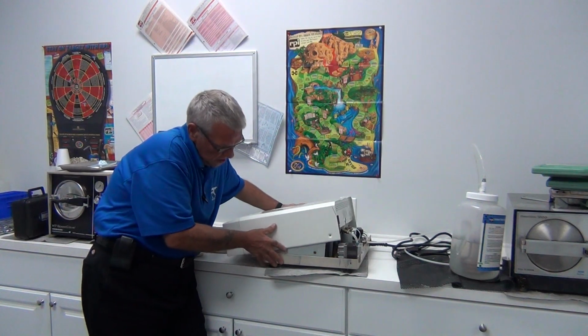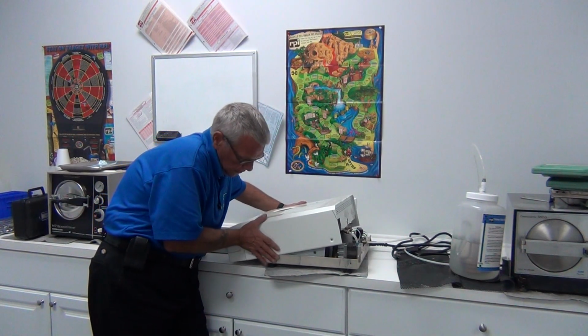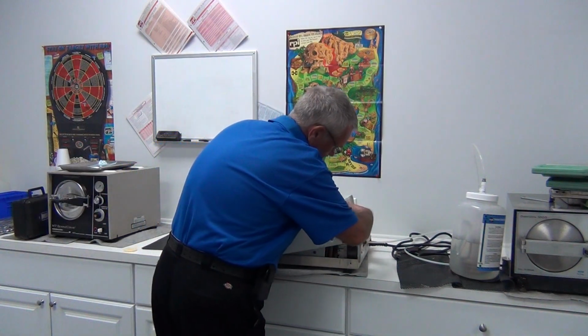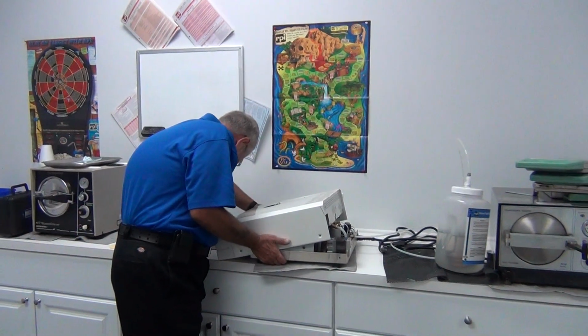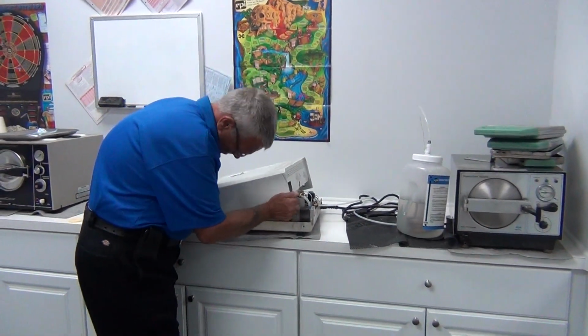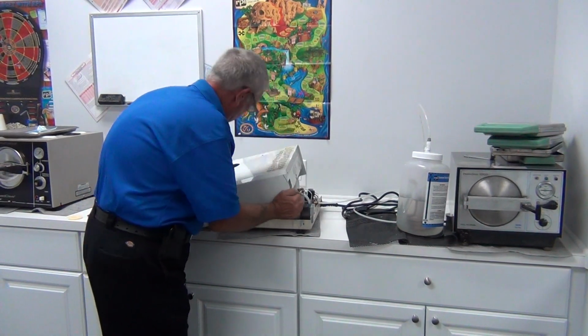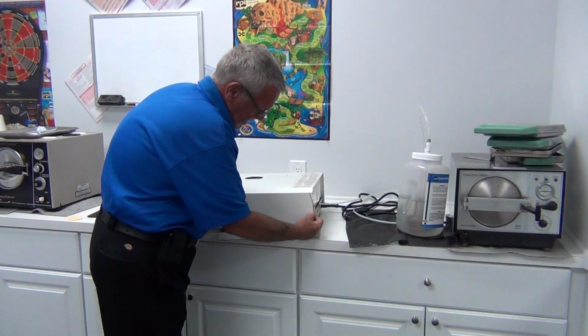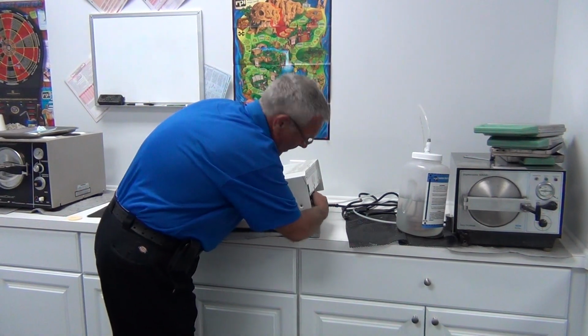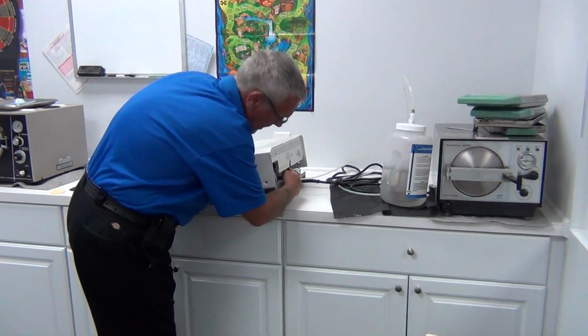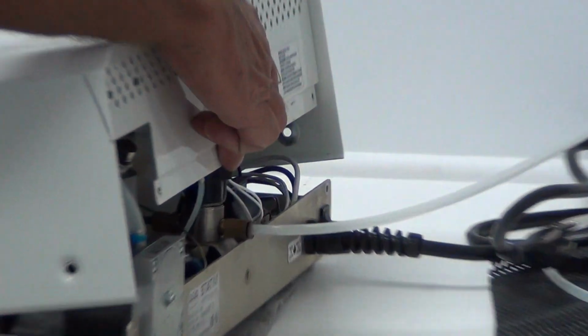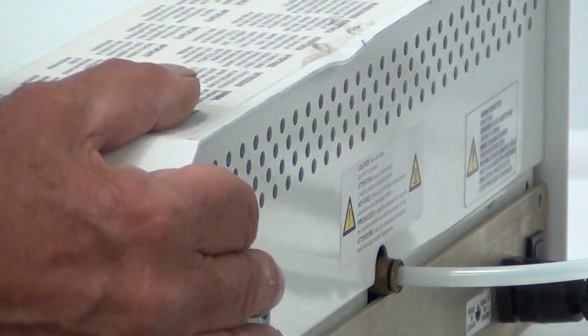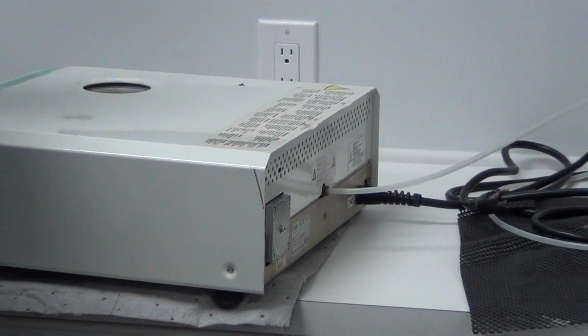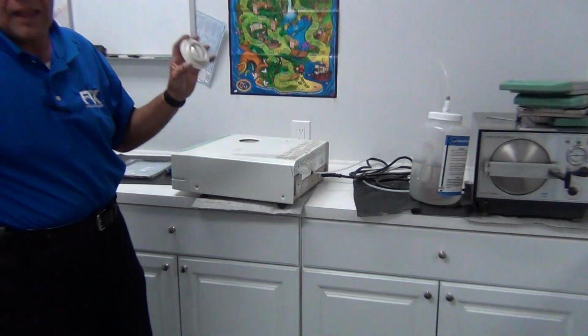So when we place the cover back on, come a little forward with the cover, making sure that we're on the outside lips. Okay? We put our fingers back here over the machinery. Push back gently until we clear the solenoid right here. It's a very tight tolerance, guys. Can you see that, Paul? Then push down gently and wiggle as you put it down. Put your screws back in. Be sure to use your reservoir cover. If they have lost this, order another one. This is very important because this has got to be kept free from debris.